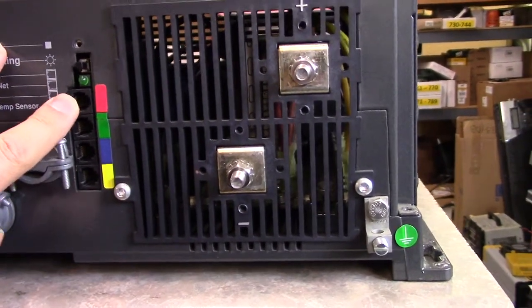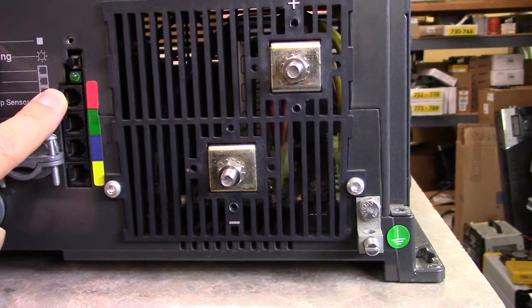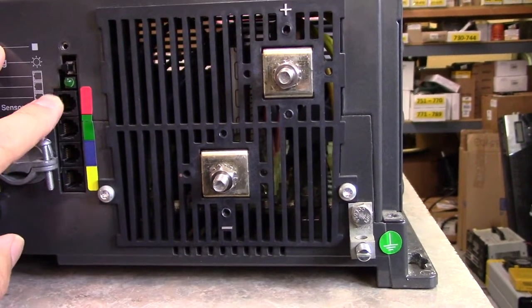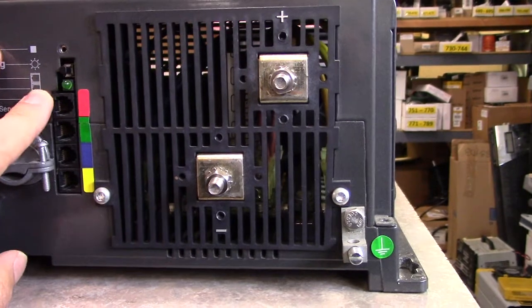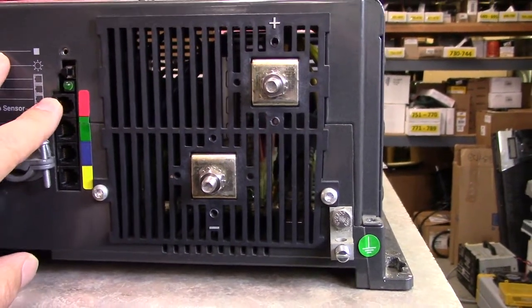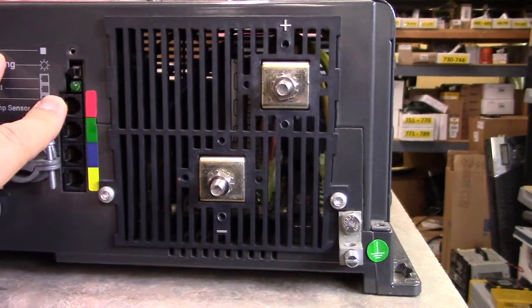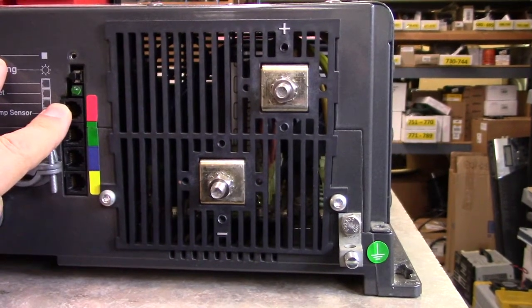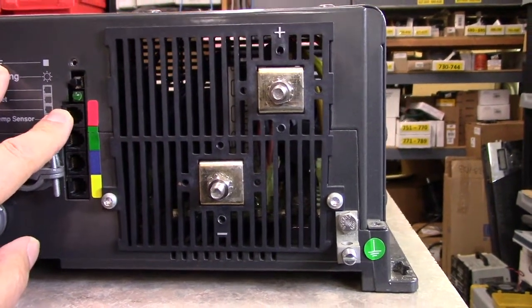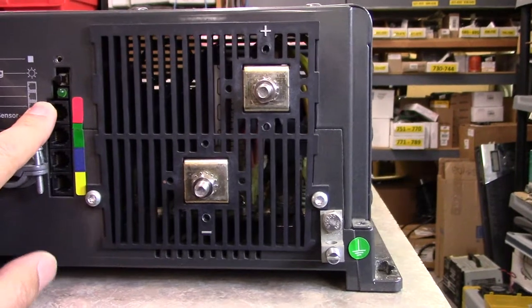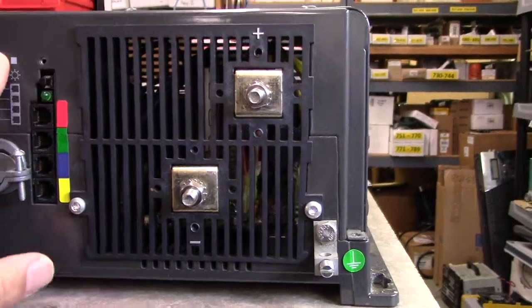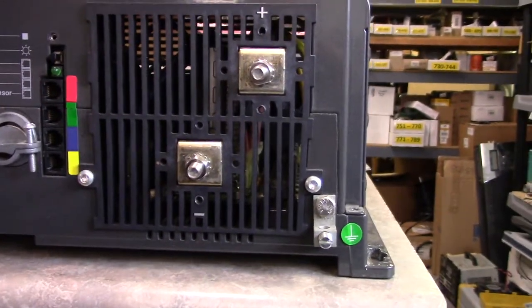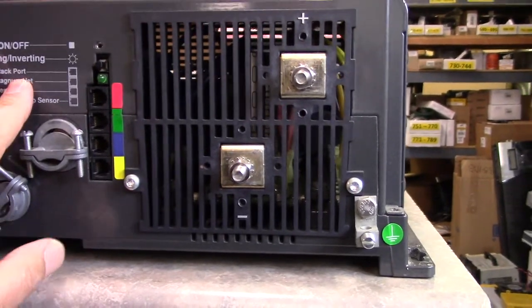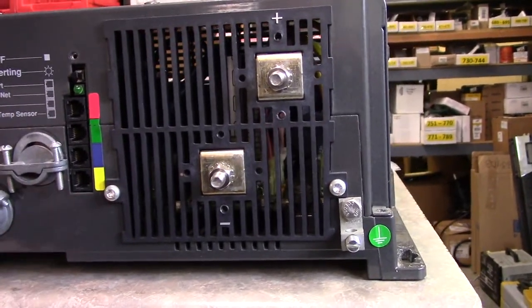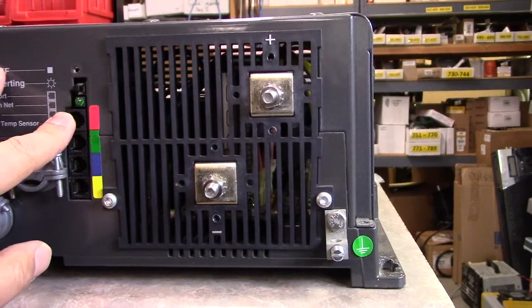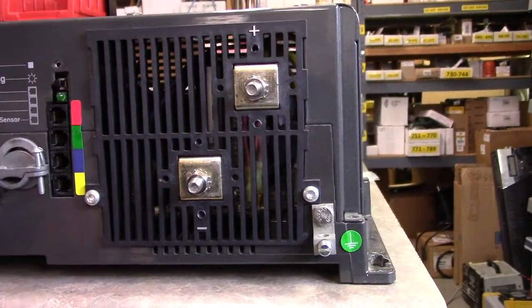This top port, the red one, is used for an external device, typically called the DC disconnect. If you see a cable in here, it's tied to a 12 volt source, and whenever that source goes to zero, the inverter will shut off. It's used to automatically shut the inverter off for storage or other reasons, or even as a remote on-off.